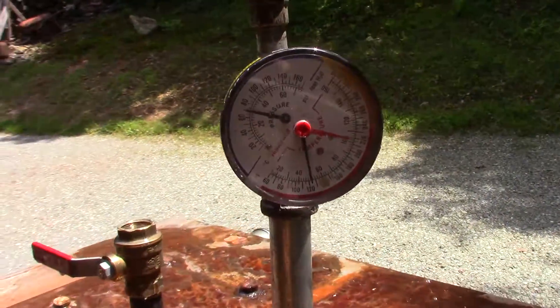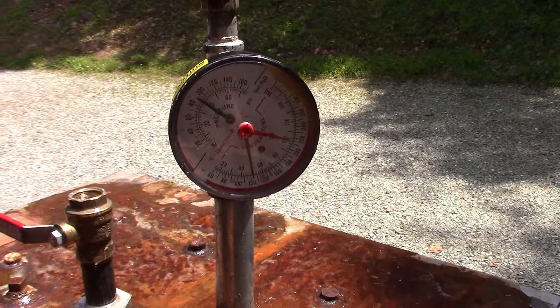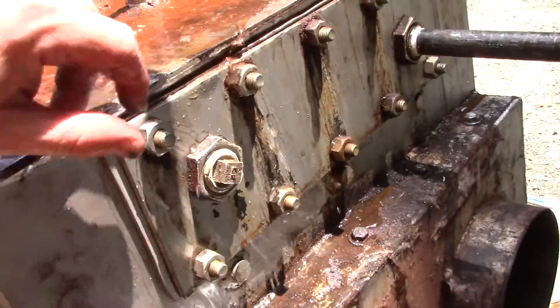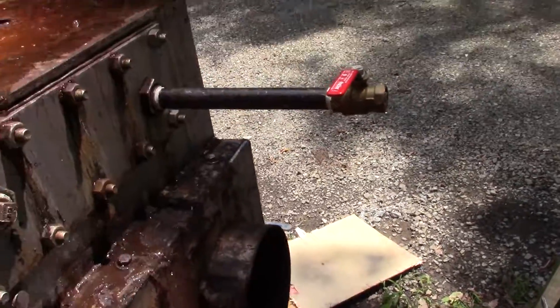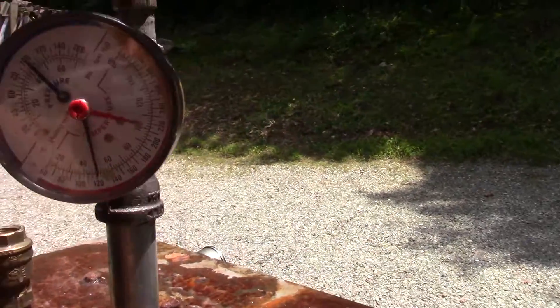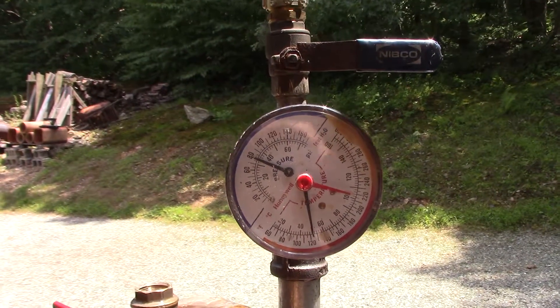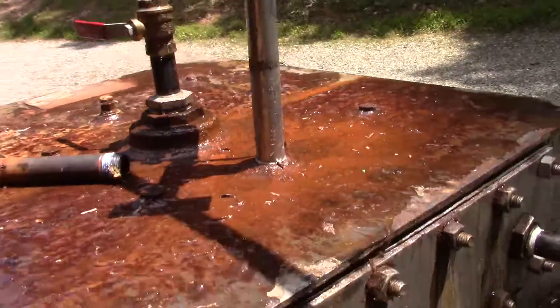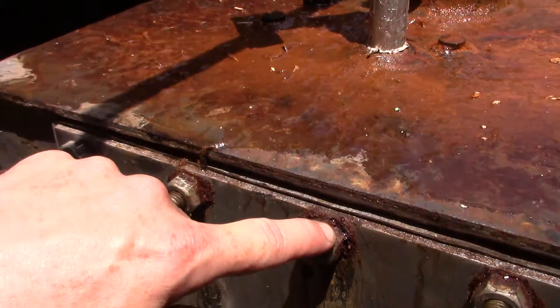Pressure it up. Okay, so the valves are shut — that's not good. Losing pressure quickly. Looks like we got a good-sized leak here — yeah, got a leak right there.